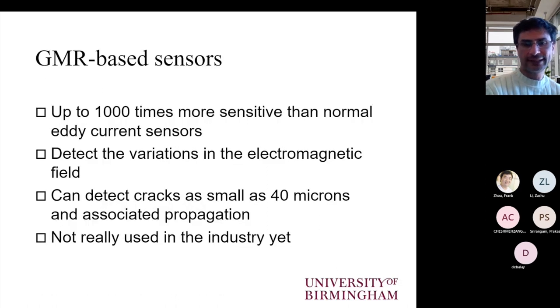Of course, in classic instruments, we use coils in order to detect electromagnetic field variations. In more advanced systems, it is possible to use Hall probes, or even better, GMR-based sensors, even though we have to take into account the orientation of the field with respect to the position of the sensor. But in theory, GMR sensors can achieve much higher sensitivity in comparison with the coil, perhaps up to 1,000 times more sensitive than normal eddy current probes. And of course, that means we can increase the signal-to-noise ratio.